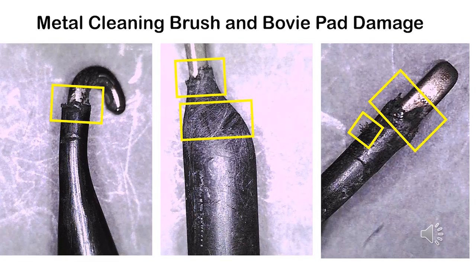Using the right tools to clean is really important. In the picture on the left, this is actually using a metal brush, which is not good on insulated devices. So what that does, it takes off the bioburden. The problem is it also takes off the insulation, which causes fragments that can actually go into a sterile cavity.